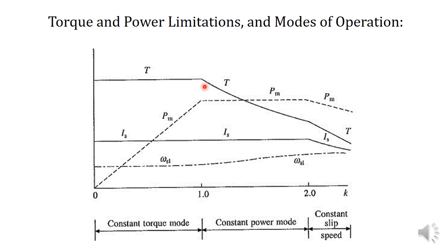So up to rated frequency, we will be maintaining the V by F ratio constant, so the torque will remain constant. So this is the constant torque region or constant torque mode of operation. And in this region, the power will be increasing. Power is not constant in this region, and we can say current is almost constant.